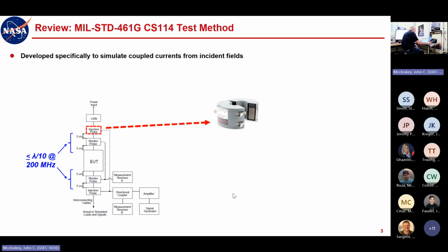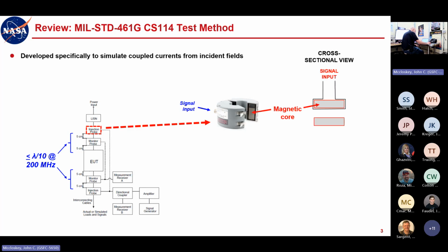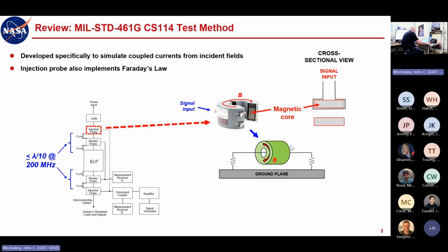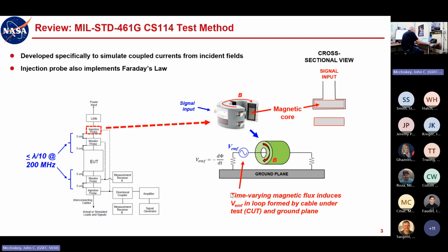The centerpiece of all of these test methods is the injection probe. Here's a cross-sectional view: you provide a signal input, and there is a magnetic core. The signal is connected to a coil of wire that goes around the magnetic core, producing a magnetic flux that goes through that core, and then that flux couples through your loop formed by the cable and your ground plane or your calibration fixture. The time-varying magnetic flux will induce an EMF, a potential in that loop formed by the cable under test and the ground plane.